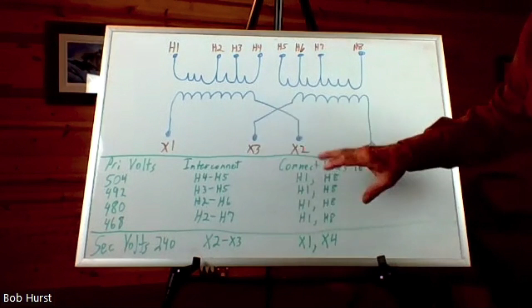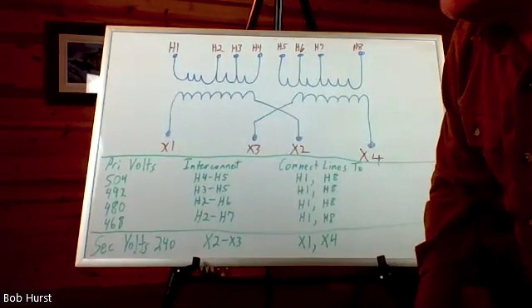So you've got multi-taps based on your primary. Your secondary right here shows - we can go into more detail later in some other lessons - but right now we're going to look at it as just a primary going to a 240 volt secondary. So this is typical of what you'll see on a nameplate with a wiring schematic on a transformer that has a multi-tap. It's a single phase transformer, and this one's going from 480 to 240.